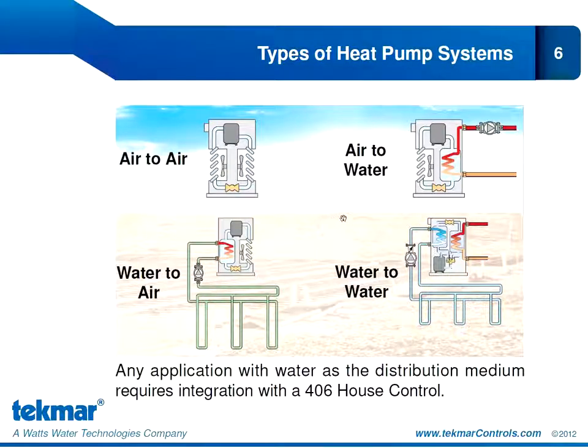On the other side of the slide, we show 2 heat pumps that use water to distribute the energy to the building. We have an air-to-water heat pump, where air is being used to gather that energy, and water is being used to distribute the energy to a hydronic system. Underneath that, we have the water-to-water heat pump, where we're using a geo source to obtain our energy, and we're using water to deliver that energy to the load in a hydronic system.